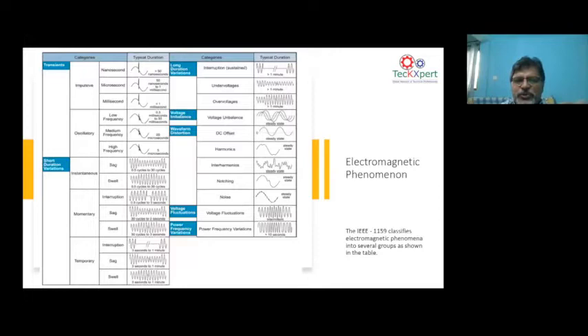Now, when you look into how to analyze this, what is meant by a transient? A transient can be an impulsive transient, it can be an oscillatory transient. And generally, where does an impulsive transient come from? If you get a lightning strike on the line or near the line, you get an impulse, a sudden jerk of voltage transient on the power line. So that is called an impulse. Now, how does that impulse behave? It behaves with a rise time, a drop time, and a peak.